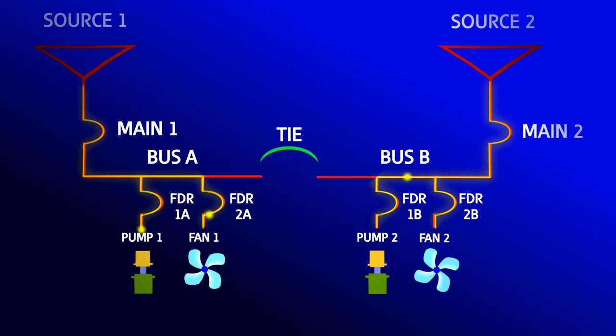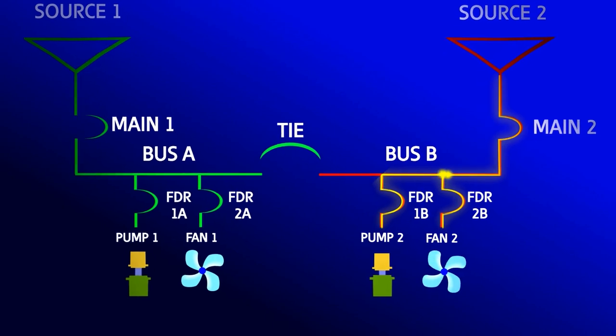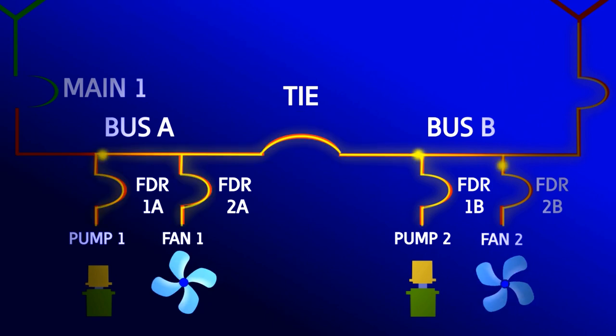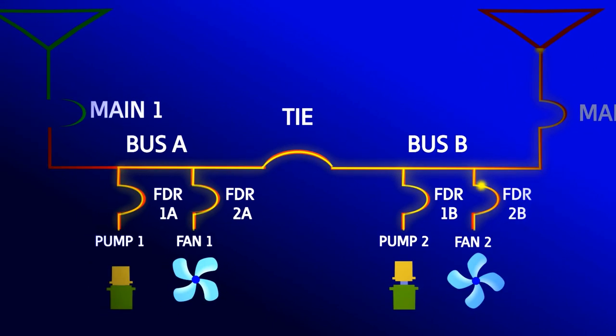In the case where the tiebreaker is open during normal operation, the loss of one source will result in the loss of half the loads. This is only temporary until the tiebreaker closes and the lost loads are powered from the remaining source.